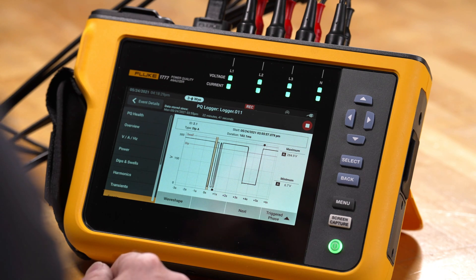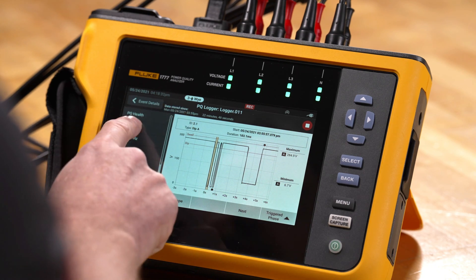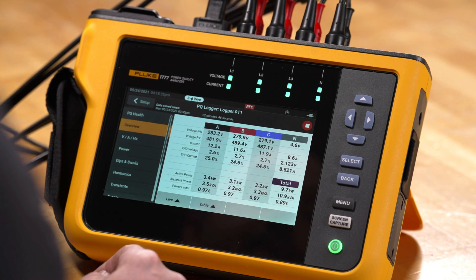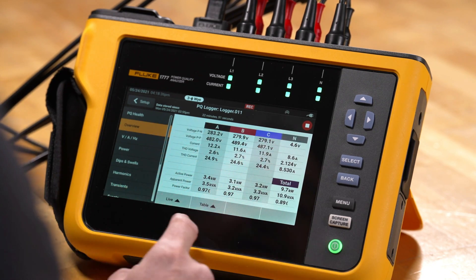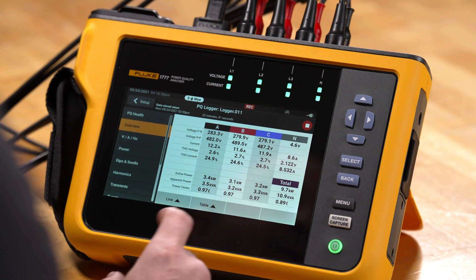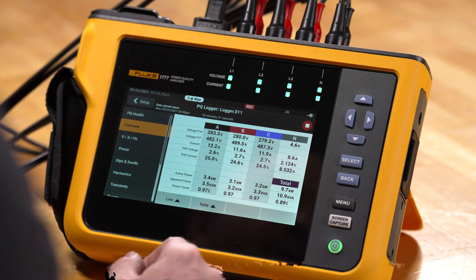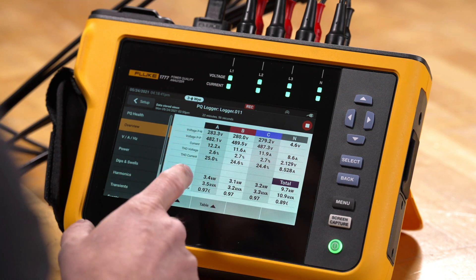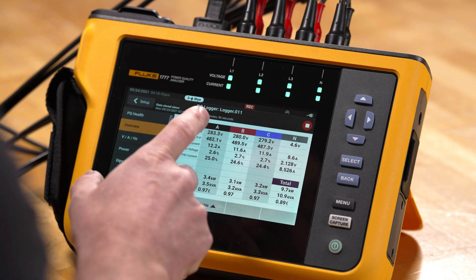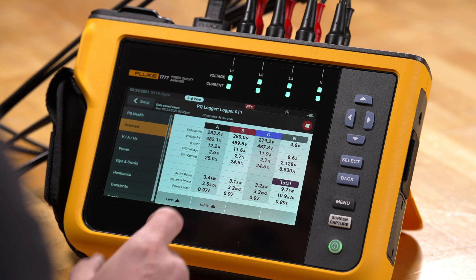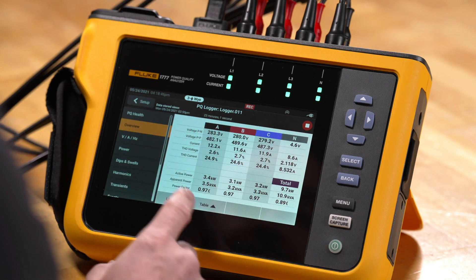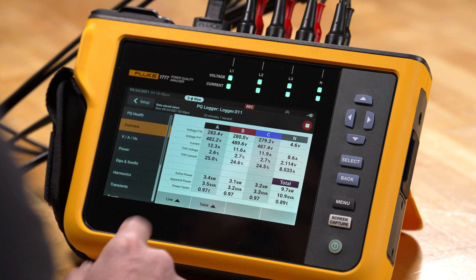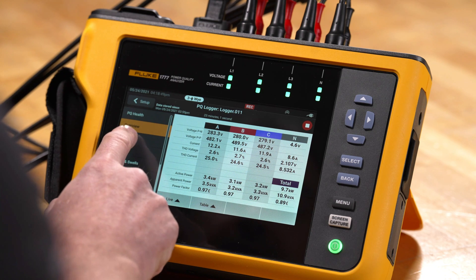The overview screen shows us the actual ongoing live measurement data. On a single screen, we can view our voltage, our currents — phase to phase and phase to neutral — and we also have active power and apparent power values.